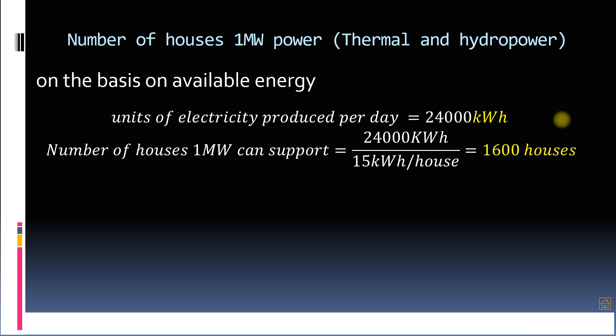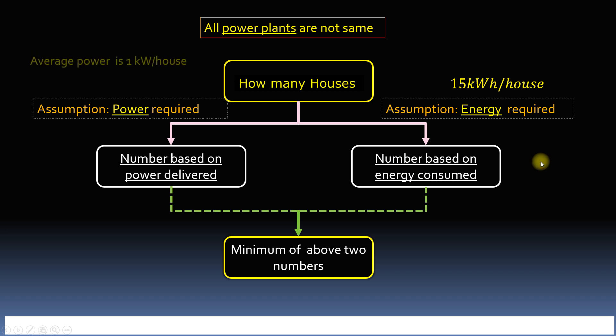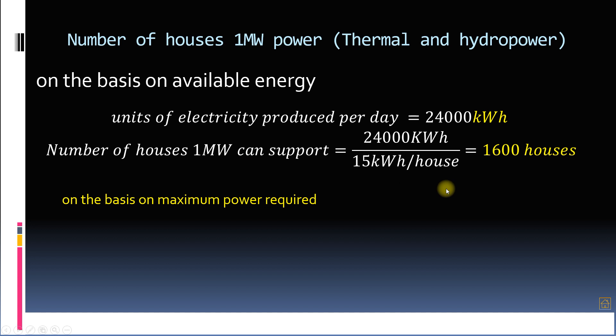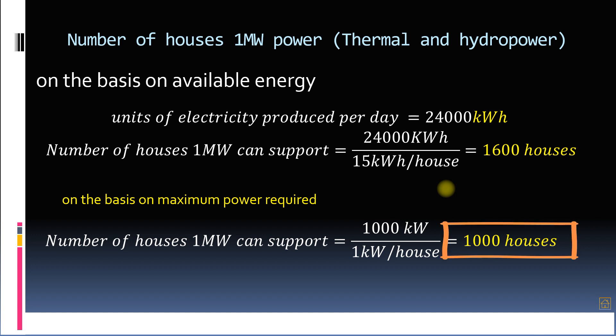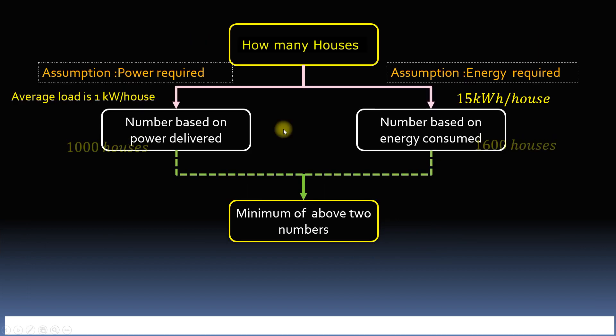Now let's calculate number of houses based on power. We have assumed that on the average maximum power of 1 kilowatt is required by each house simultaneously. Therefore, the number of houses that can be supported will be equal to 1000 kilowatt divided by 1 kilowatt per house equal to 1000. So we can say that the least of two numbers, that is 1000 houses, can be supported by 1 megawatt power plant.